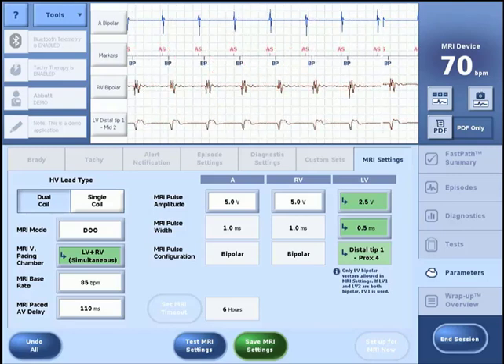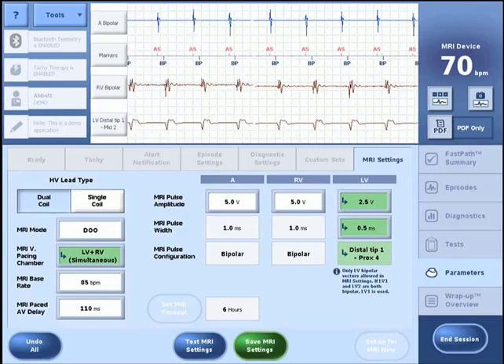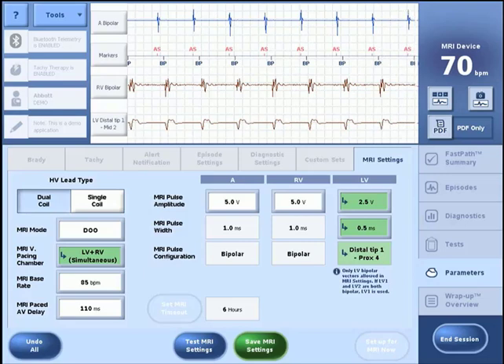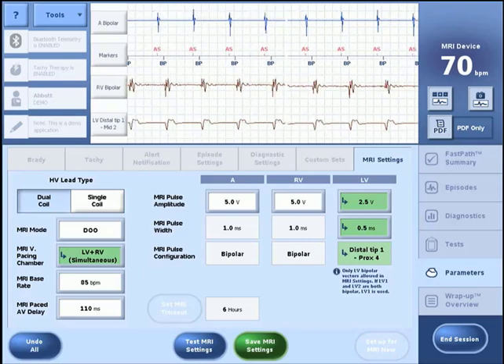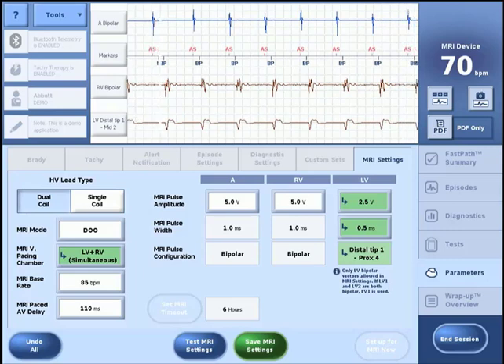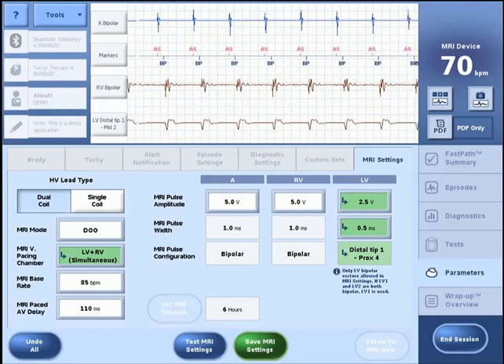High voltage lead impedance tests are an important system integrity check as part of the MRI setup process. Lead fractures or other damages to the leads may cause changes in the electrical properties of the system that make the system unsafe for an MRI scan. Patients with damaged leads may be harmed if an MRI scan is performed.